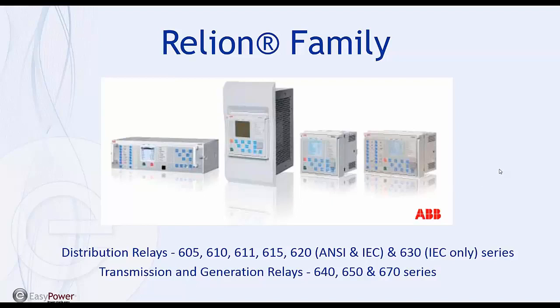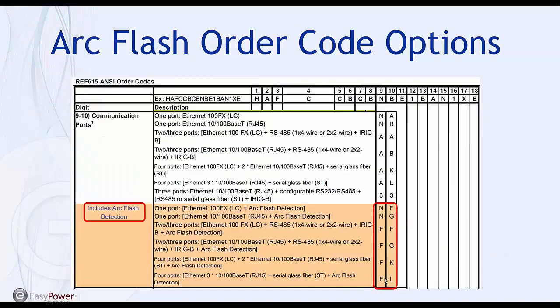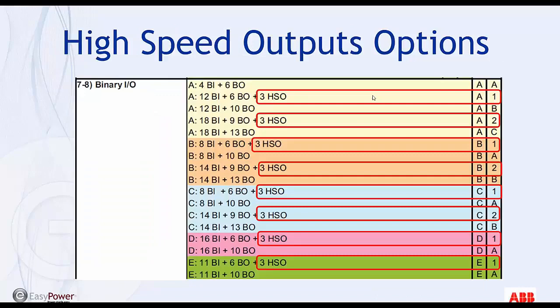So in order to get the right relay, you have to have the arc flash option, or have the right communication module selected that has the arc flash detectors on that card. That's what that is. And then the other order code option that's vital is having the high-speed outputs. You need to select an option that gives you the high-speed outputs.